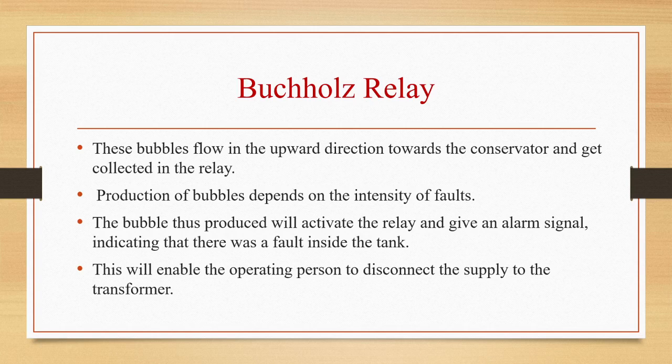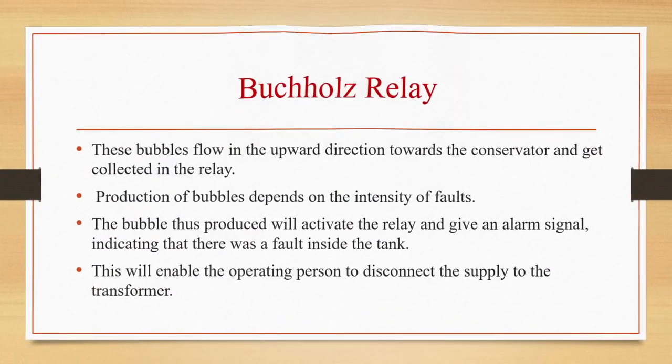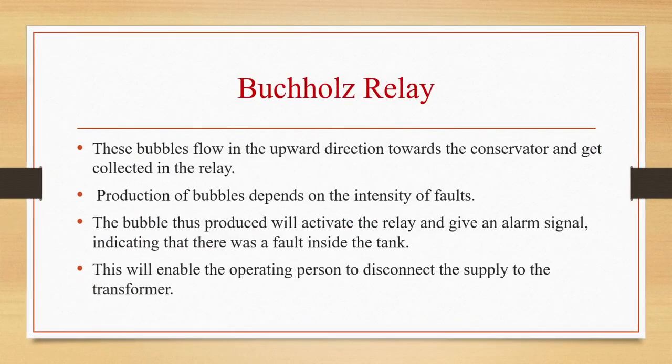Production of these bubbles depends on the intensity of faults. The bubbles produced here will activate the relay and give an alarm signal indicating that there was a fault inside the tank. So this will enable the operating person to disconnect the supply to the transformer. So in this way, the Buchholz relay is acting like a protective device to the transformer.